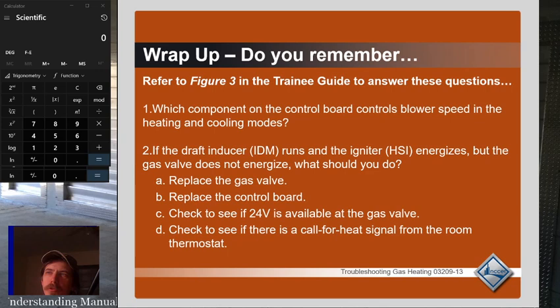Which component on the control board controls blower speed in the heating and cooling modes? The indoor draft inducer runs and the igniter energizes, but the gas valve does not energize. What should you do? Replace the gas valve, replace the control board, check to see if 24 volts is available at the gas valve, or check to see if there's a call for heat signal from the room thermostat. The answer there would be check to see if 24 volts is available at the gas valve, because the draft motor comes on, the pressure switch closes, then the hot surface igniter energizes, then the gas valve should come on.